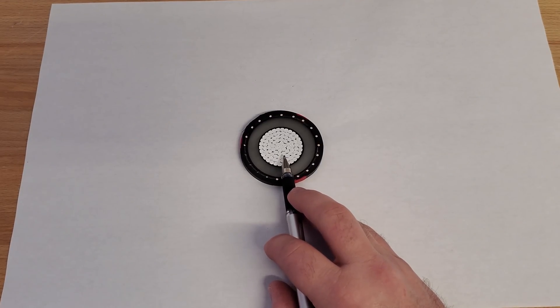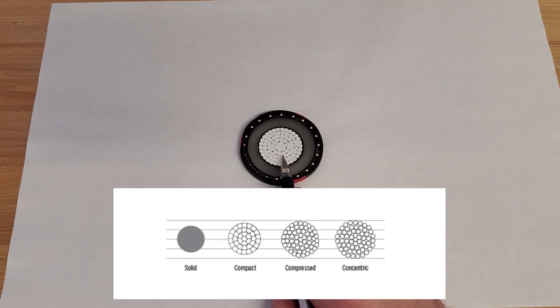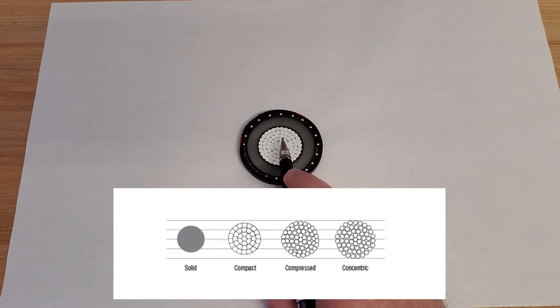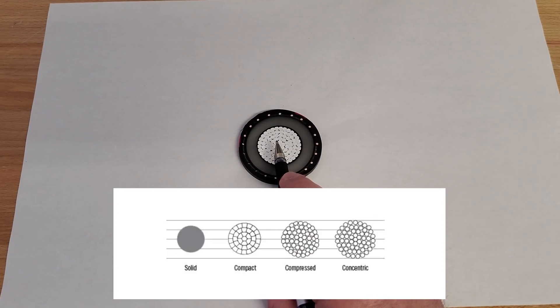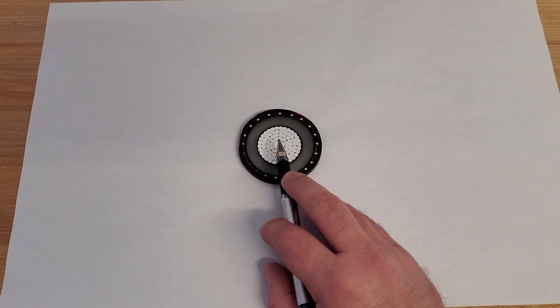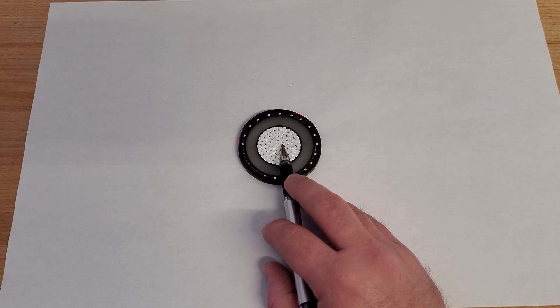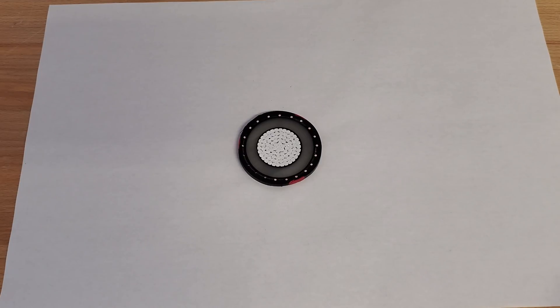There's a number of different types of conductor. There's solid conductor, which is just one solid piece of metal. You've got stranded, which is the configuration this is. And then you have compressed, where in the process they compress these together. And then the compact conductor. The compact is the second most efficient, solid being the first. But when you're installing things in conduit, there's no way you can have this be a solid piece of aluminum. There's no way you could install it. There's no way you could pull it through pipe.